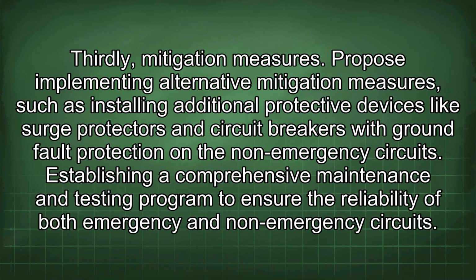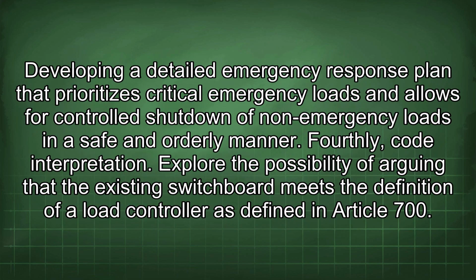modification. Thirdly, mitigation measures. Propose implementing alternative mitigation measures, such as installing additional protective devices like surge protectors and circuit breakers with ground fault protection on the non-emergency circuits. Establishing a comprehensive maintenance and testing program to ensure the reliability of both emergency and non-emergency circuits. Developing a detailed emergency response plan that prioritizes critical emergency loads and allows for controlled shutdown of non-emergency loads in a safe and orderly manner.